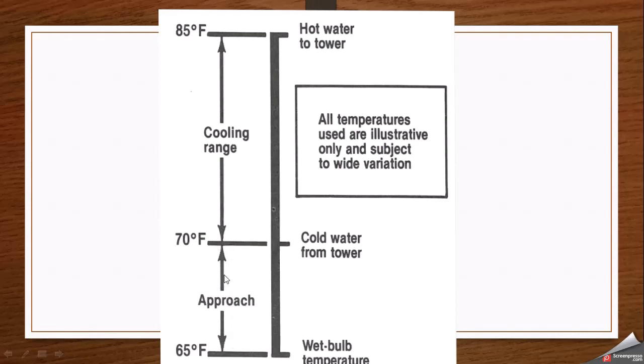However, if the wet bulb temperature drops to 55°F instead of 65°F while the cold water temperature remains at 70°F, the approach delta becomes 15°F instead of 5°F — a larger value — meaning the efficiency of the cooling tower decreases. These terms explained in this video are very useful and help to understand the concept of the cooling tower and how temperature differences play an important role in its operation.